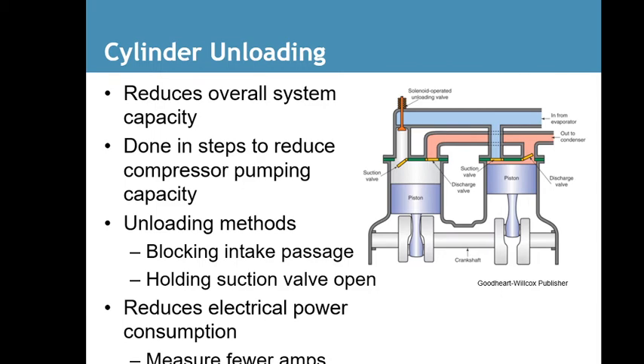Cylinder unloading. It reduces overall system capacity, done in steps to reduce the compressor's pumping capacity. Unloading methods: blocking intake passages, holding the suction valve open. This reduces electrical power consumption and measures fewer amps. So this is the concept of riding a bicycle from a stop uphill. Imagine doing it on a constant basis. What this does is lower pressure by letting some of the cylinder's backup pressure be unloaded onto the low side. That way it's not so hard for the compressor to do its job.